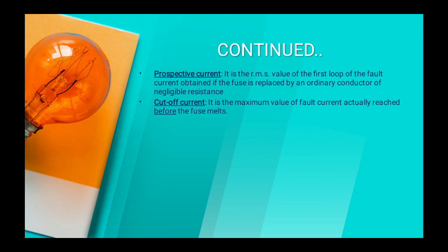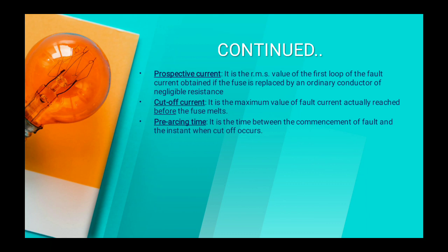Cut-off current. It is the maximum value of fault current actually reached before the fuse melts. So before melting of the fuse, the maximum value of current — after the cut-off current is exceeded, the fuse gets melt. Pre-arcing time. It is the time between the commencement of fault and the instant when cut-off occurs. That is the time between when the fault occurs and the instant when the fuse melts.